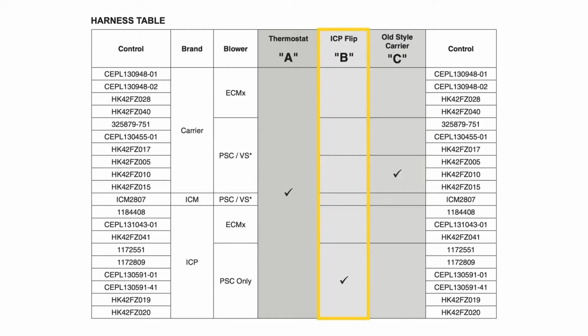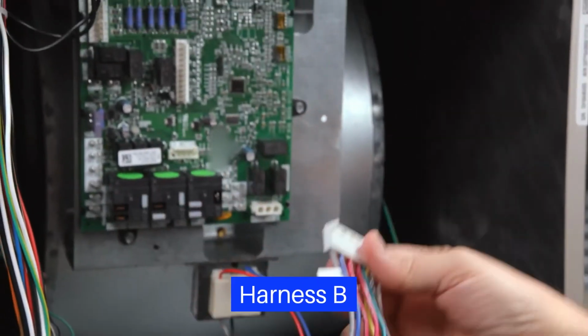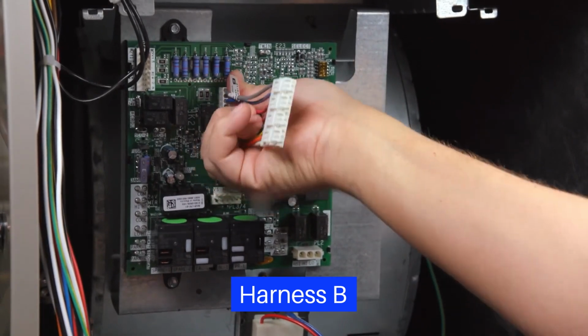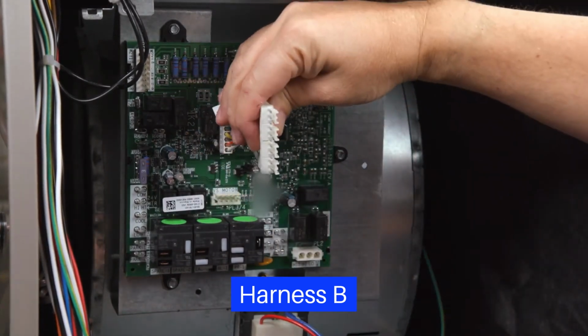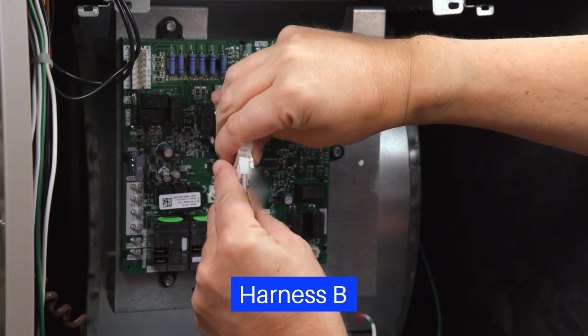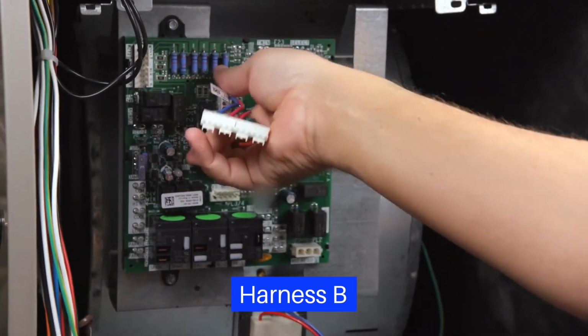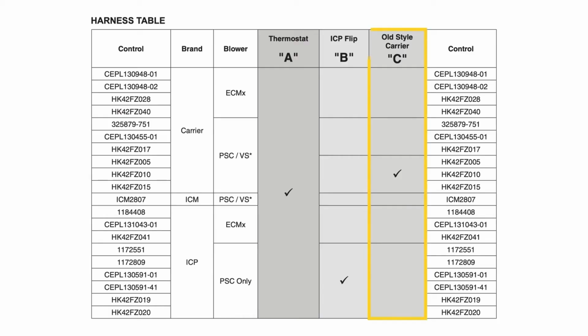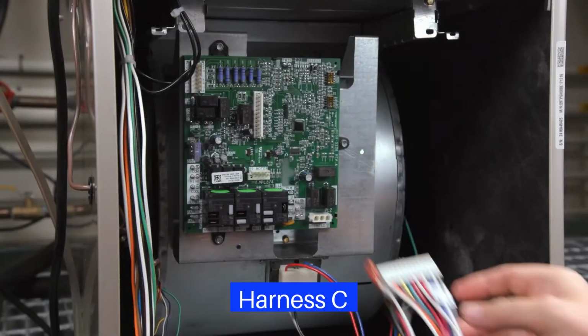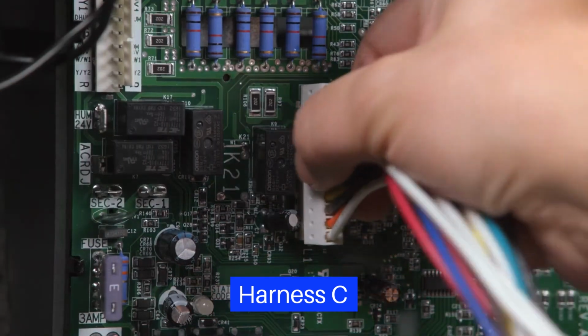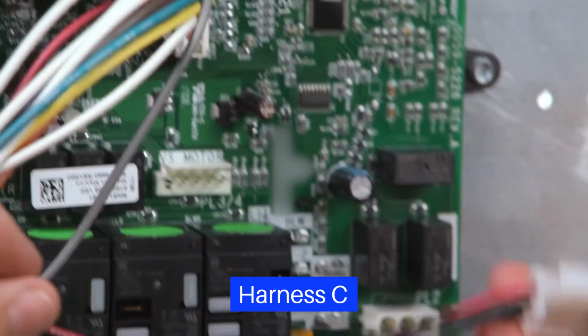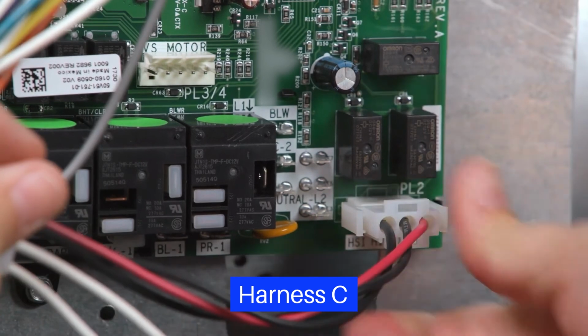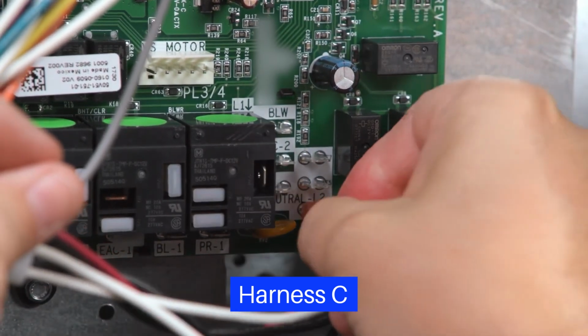Use harness B for ICP furnaces with PSC-only blower motors to connect the furnace wiring to the Carrier ICP inline plug. Because of the locking polarized tab on the inline connector, you cannot simply reverse the existing wiring. Using harness B flips the pins and allows them to match up correctly. Harness C allows older Carrier PSC furnaces to convert from a Molex connector to an inline connector. If required, plug the harness into the inline connector, the 3-pin Molex into the HSI and inducer power plug, and connect the HSI and inducer neutral wires to the neutral L2 terminals.